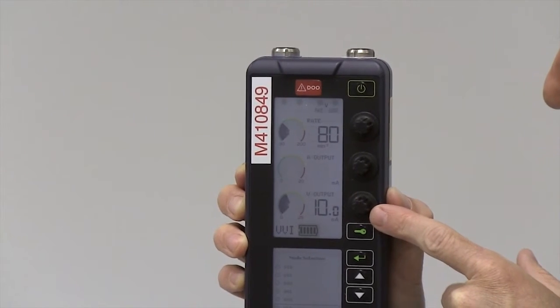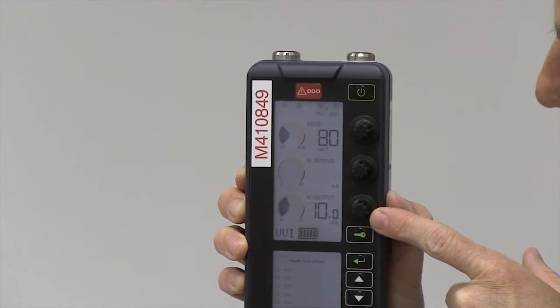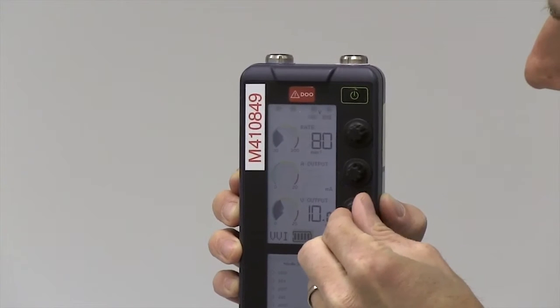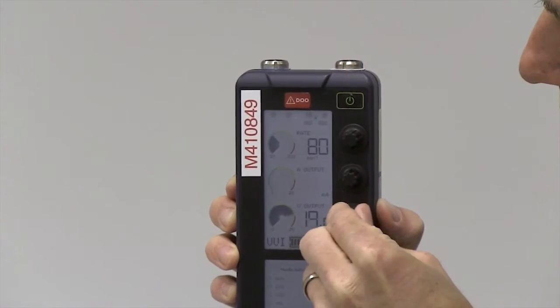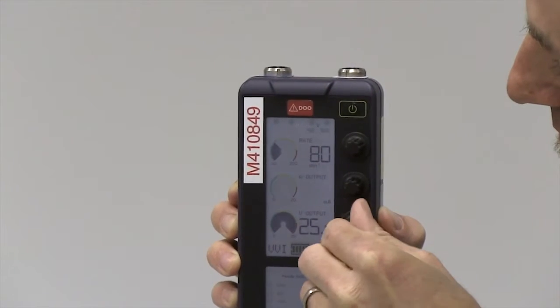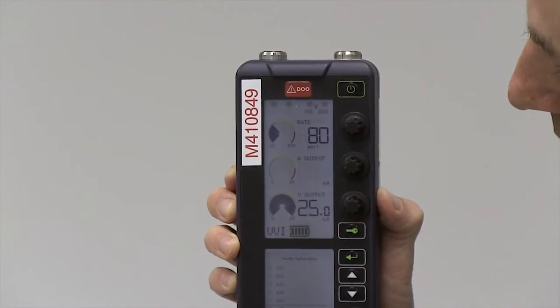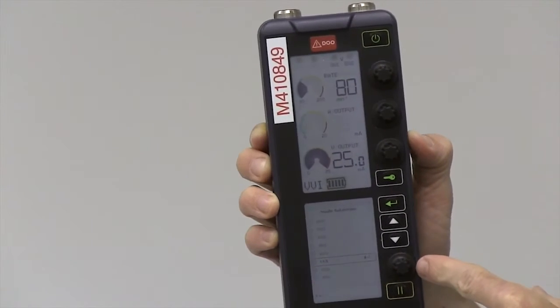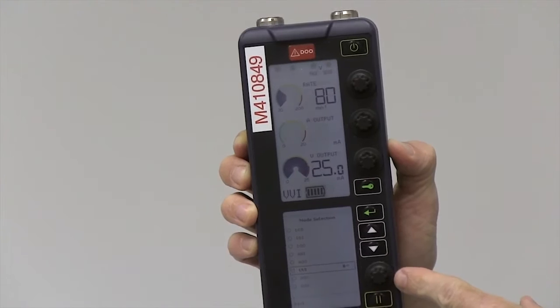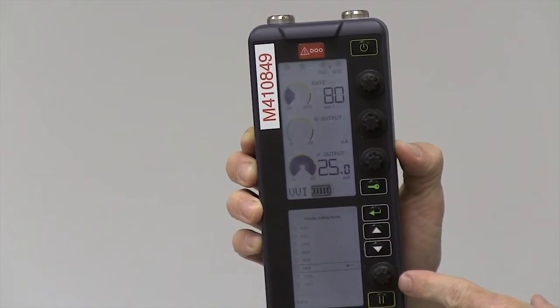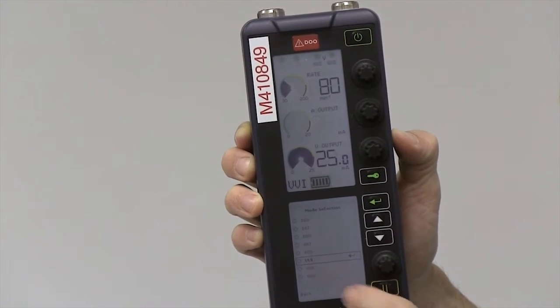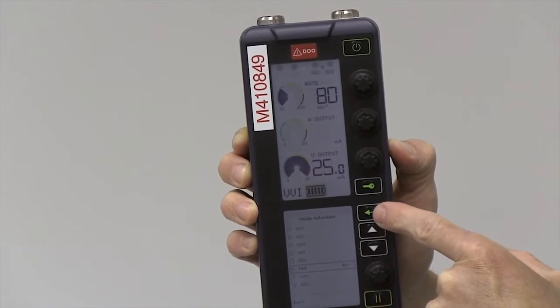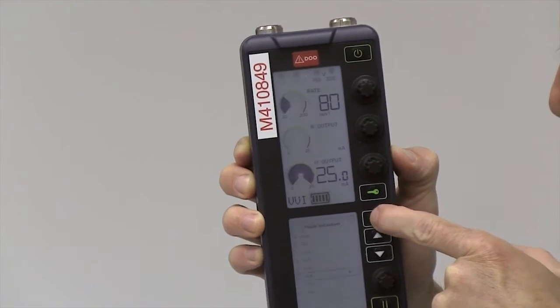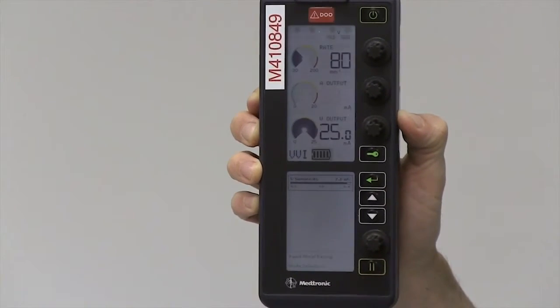The third dial is the ventricular output. I like to turn this dial to the maximum all the way to the right. Now, when we next get to the bottom screen of the pacemaker generator, you will notice that we are now in VVI mode. We want to select the arrow or selector button to be able to adjust the sensitivity.